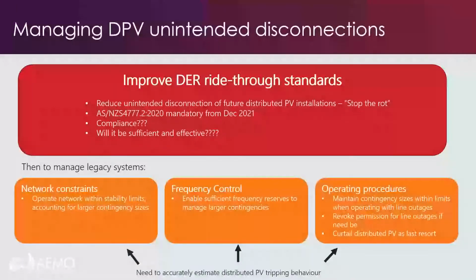So we are now watching that very actively in South Australia. In some periods, we need to revoke permission for line outages to occur where we can't handle the contingency sizes because of the amount of PV that will be online. And as a very last resort, we have procedures in place to curtail distributed PV systems if need be, because there's no other way to maintain a secure power system with the amount of PV that's operating. All of this is informed by estimates of PV tripping behaviour from the existing fleet, which I'll talk about more in a second.